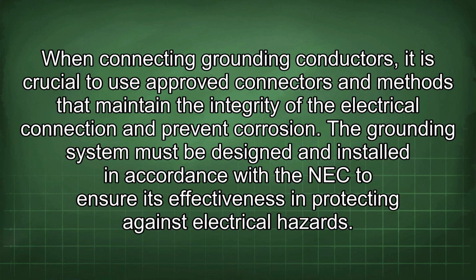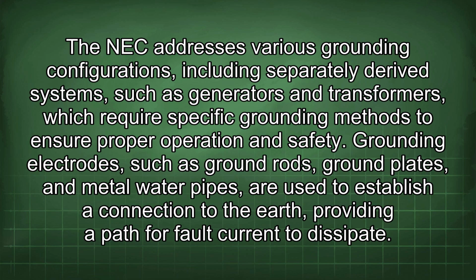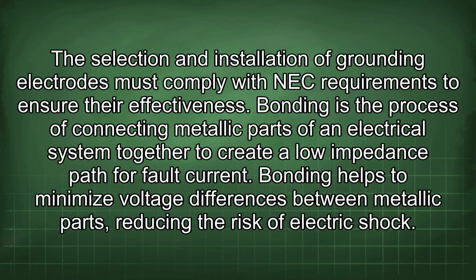The NEC addresses various grounding configurations, including separately derived systems such as generators and transformers, which require specific grounding methods to ensure proper operation and safety. Grounding electrodes, such as ground rods, ground plates, and metal water pipes, are used to establish a connection to the earth, providing a path for fault current to dissipate. The selection and installation of grounding electrodes must comply with NEC requirements to ensure their effectiveness.